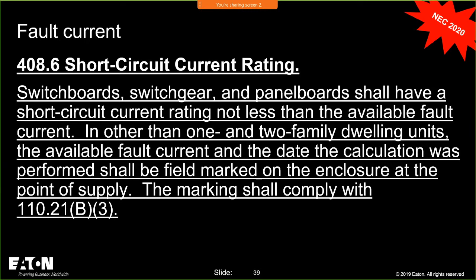I'm just looking through 408 panelboards. Let's take a look at panelboards. In addition to the requirement of 408.30, a panelboard shall be protected by an overcurrent device. That just talks about protection, because part 3 is panelboards, so let's look in part 3. Snap switches, supplied through a transformer, backfed devices, damp or wet locations, grounding of panelboards, panelboard orientation. No, there's nothing in part 3 that says I need a marking of available or marking of the short circuit current rating.